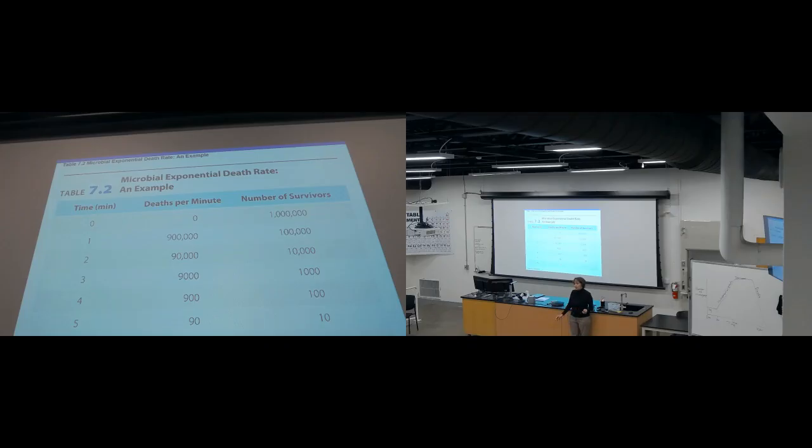So no matter if it's one microbe, you cannot say, well, the autoclave got broken at minute 6 and I stopped the sterilization process, and then report in your sheet for sterilization that this instrument is almost sterile, you can use it.